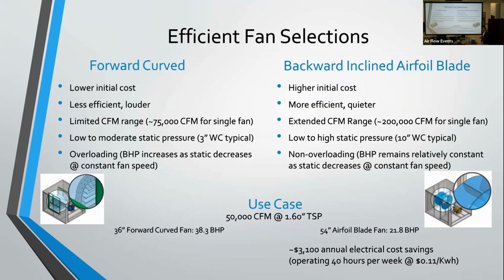So it's a pretty significant difference in electrical costs, especially when you consider buildings that are 2, 3, 4 times the size of that. So really the forward curve fans are popular and they have a lot of appeal because of their lower initial cost. But really over the long run, your backward inclined airfoil blade fans are going to be the way to go. And that's where the market is trending these days also.